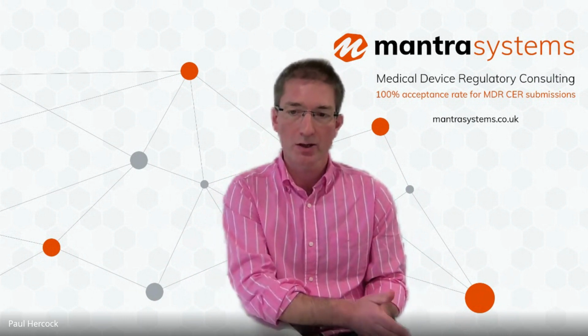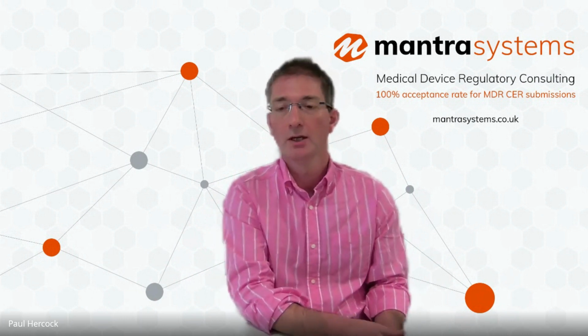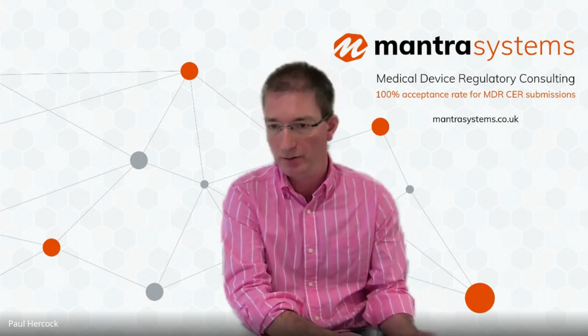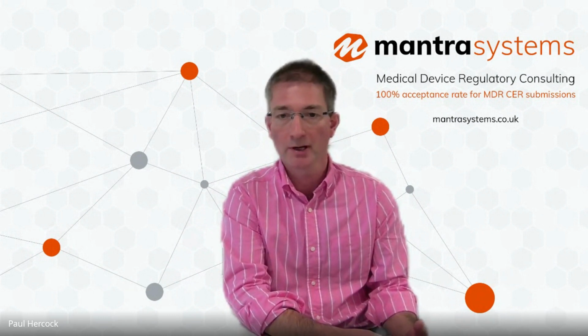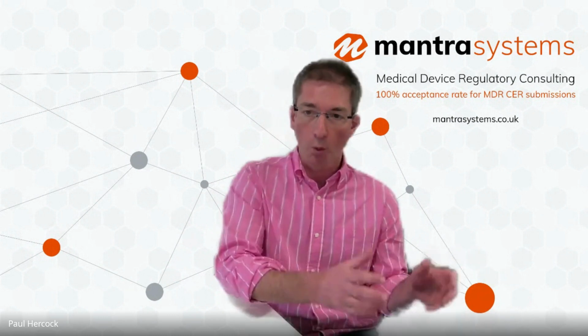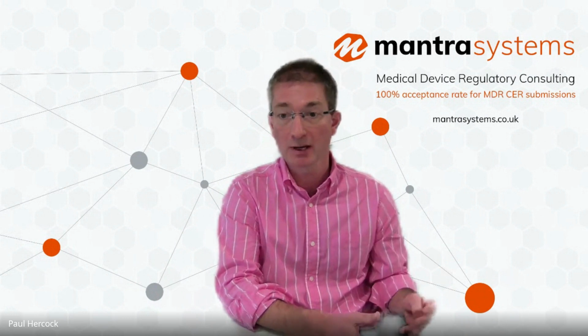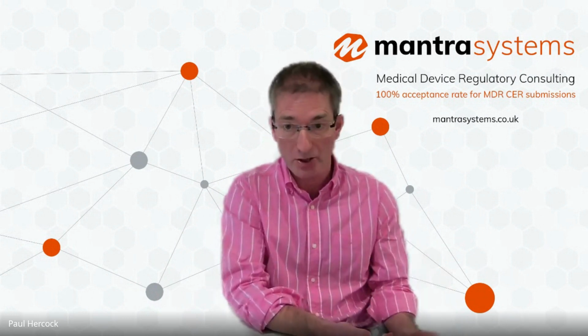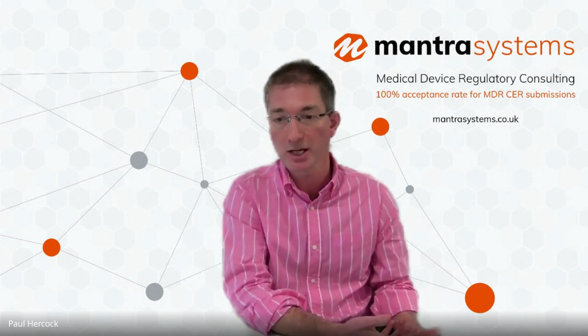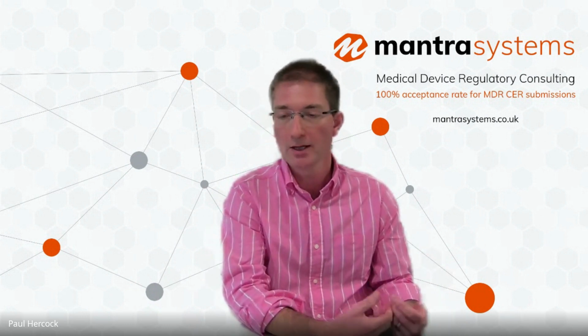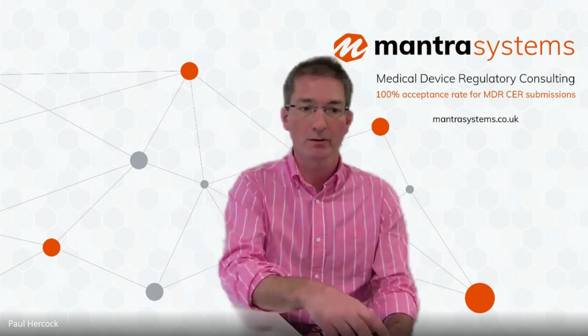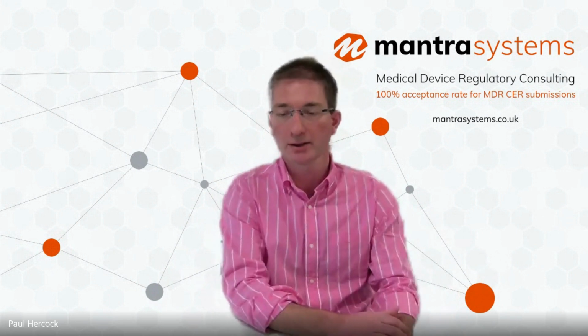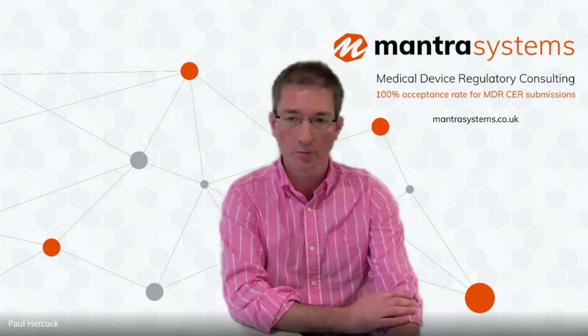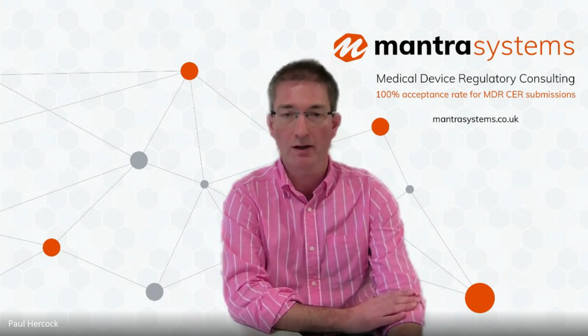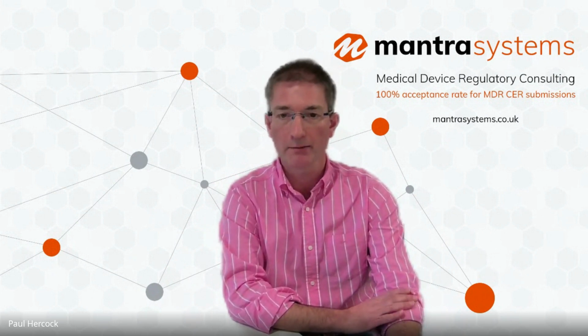So I recommend making a start on the SOTA review as early as possible. You can then start populating the other sections, such as section 3, which we talked about before, which is principally in relation to information about the device itself, while the SOTA review is underway. You can also start collating data relating to the subject device. And so you can do a literature review for the subject device. You can go to the vigilance databases, the adverse events databases like BfArM, and start collating data so that by the time the SOTA review finishes, you've got everything in place to make your comparison. But I think the basic principle would be start with the most time-consuming sections first, if possible, and have a team of people working in parallel.